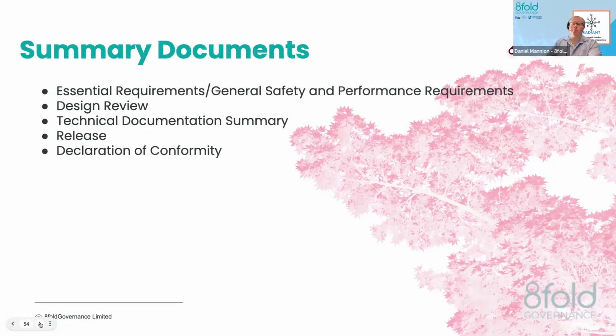And then you'll have a set of documents that summarize the technical file. So there's a checklist, the essential requirements for the UK, or the general safety and performance requirements for the EU. That is a list of all the medical device requirements, and you have to create a checklist and say how you've met them. A design review is a summary of what you've done and everyone approving that it meets the requirements and the expectations that you've set for the software.